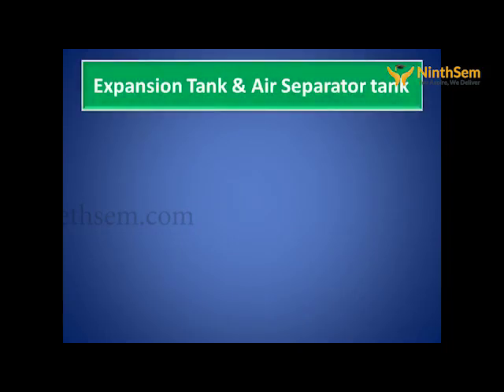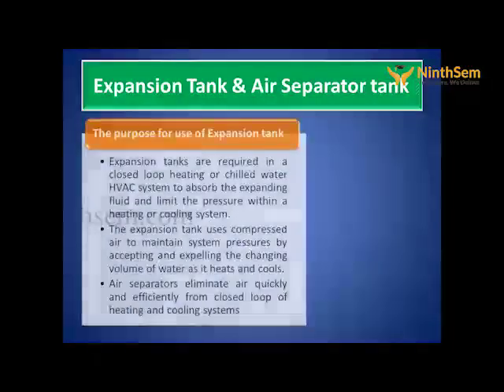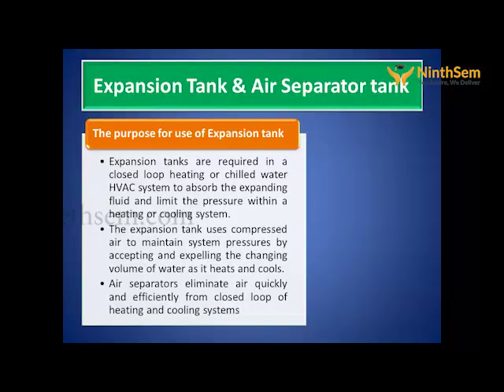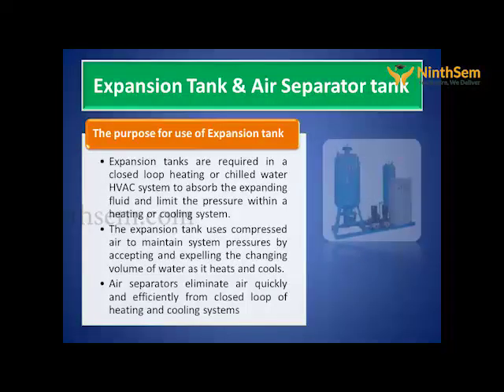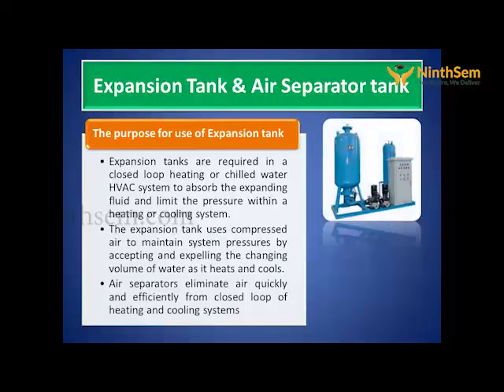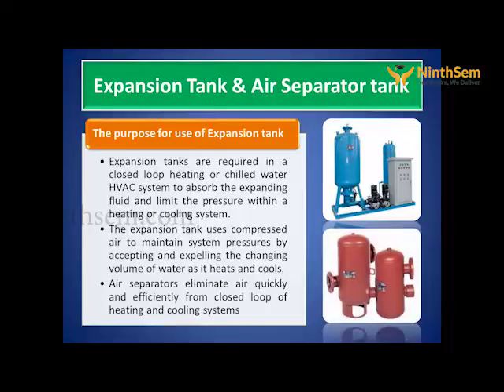Now, expansion tank and air separator. The purpose of use of expansion tank in chill water system is: first, expansion tanks are required in a closed loop heating or chill water HVAC system to absorb the expanding fluid and limit the pressure within a heating or cooling system. The expansion tank uses compressed air to maintain system pressure by accepting and expelling the changing volume of water as it heats and cools.